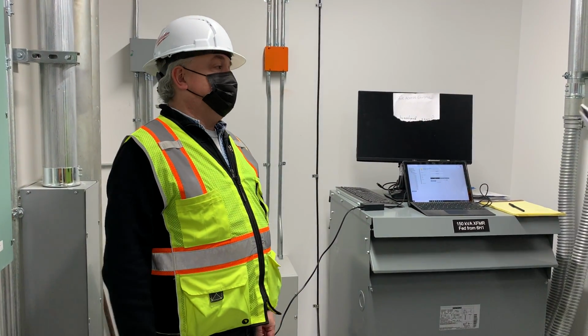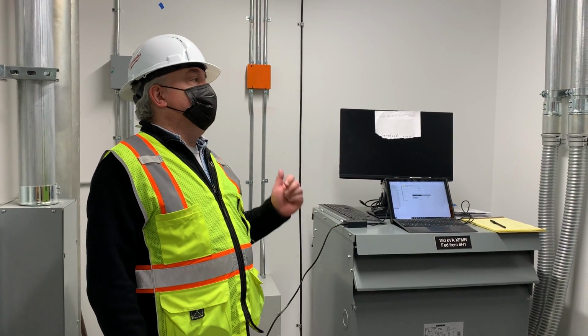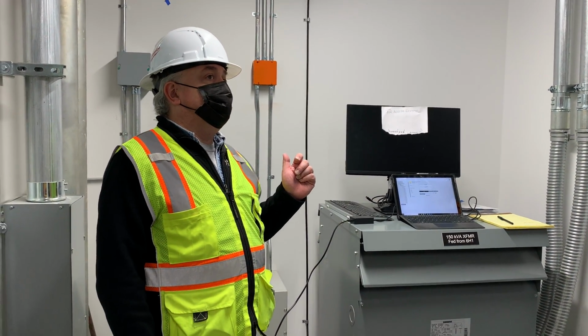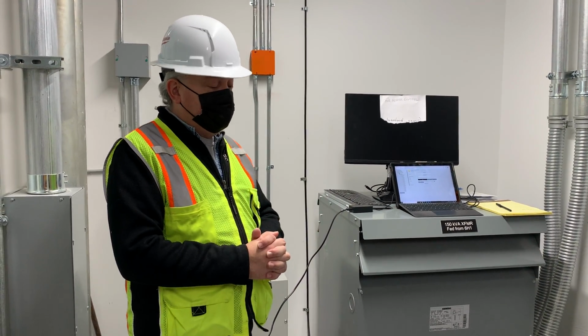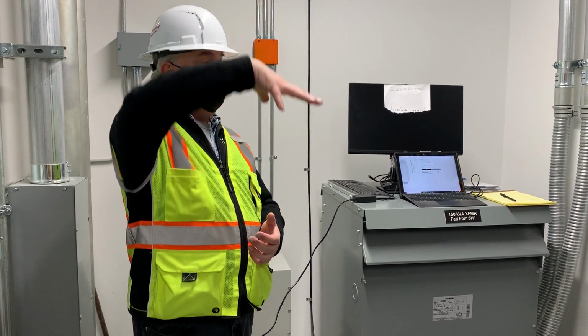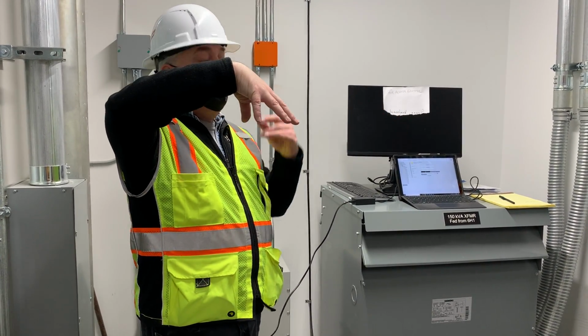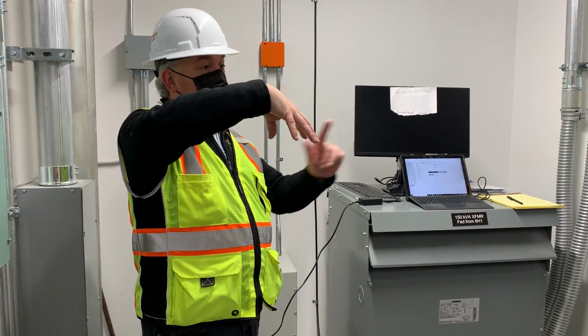So you said it has to trigger both ultrasonic and infrared in order to do it? Yes. Maybe I'm telling you things you already know, but the PIR side of a sensor, I consider it to be something like an upside-down sea urchin with all the spines. What it's looking for is heat moving from one spine to another.